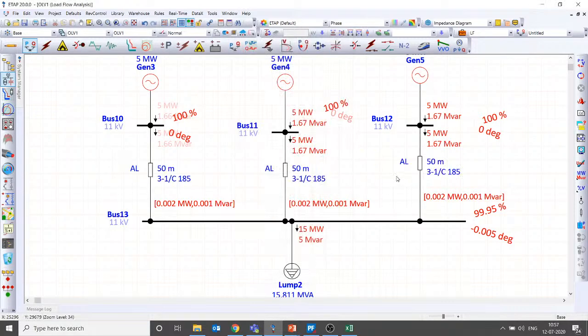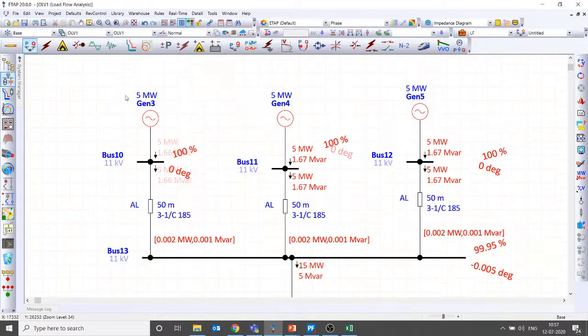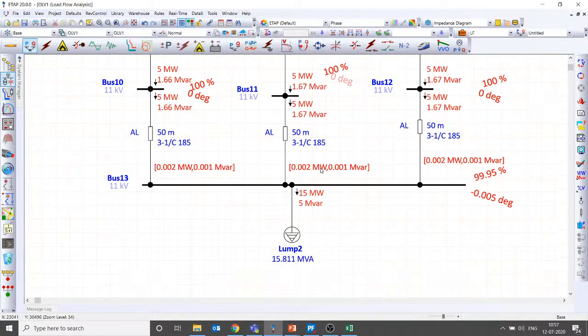I have given 50 meters each, and I have given the loads the same, so the load is shared equally by all three generators, and the losses are almost nil. So each generator is generating 5 megawatt to meet this demand of 15 megawatt.